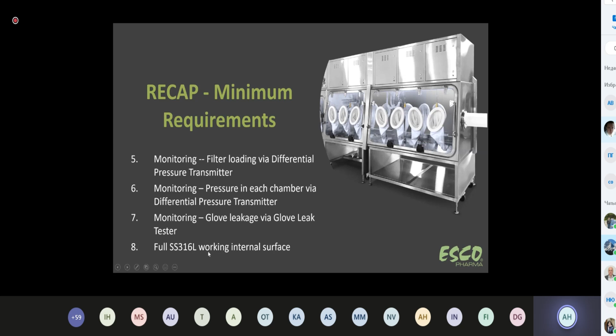Monitoring: you also will need to monitor the integrity of the filter. You need to check if the filter is fully loaded or not. This is monitored using a pressure sensor, what we call a differential pressure transmitter. We also need to monitor the pressure value in each chamber, and we also use this differential pressure monitor. We recommend the customer use a glove leak tester just to make sure that everything is fully tight. And the inside, at the minimum, is full stainless steel 316.